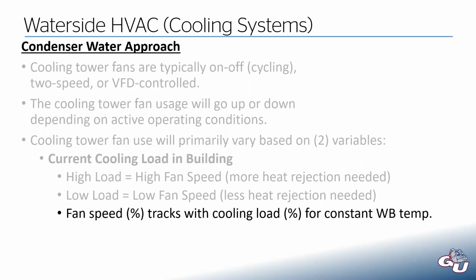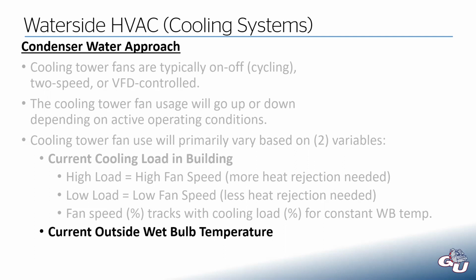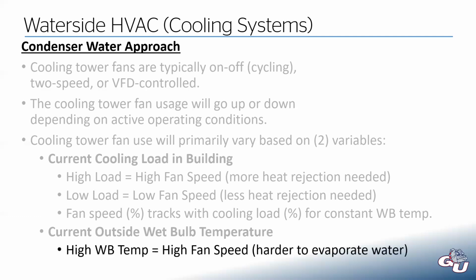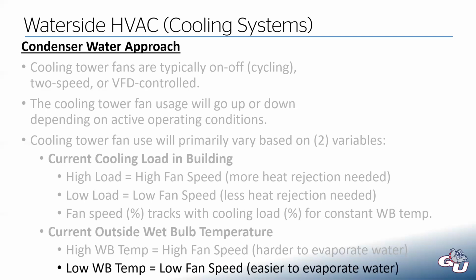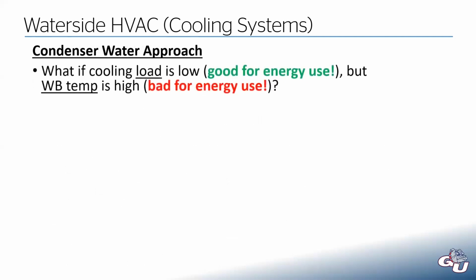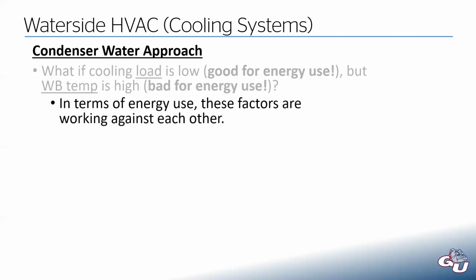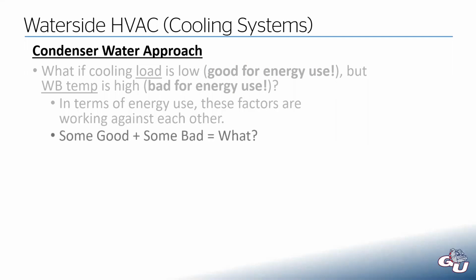That's variable one. The second variable is the current outside wet bulb temperature, which I already mentioned earlier. If we have a high wet bulb temperature, it's going to lead to a high fan speed or cycling because it's harder to evaporate the water. If we have a low wet bulb temperature, it'll mean a low fan speed because it's easier to evaporate the water. But what if we're in this scenario where our cooling load is low, which is good for energy use because that means our fan doesn't have to work as hard, but our wet bulb temperature is high, which is bad for energy use. So these factors are working against each other. One is good, one is bad. What's the resultant outcome there?